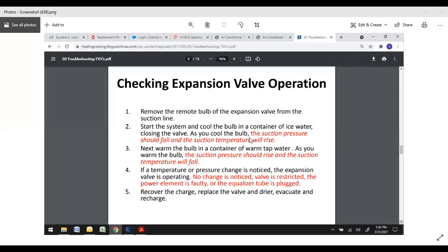Okay, well, you're checking the expansion valve. This is actually fairly easy because with Rheem, it's actually outside the cabinet. So the best way to check this is to remove the remote bulb of the expansion valve from the suction line. You can start the system. Two ways you can do it, or both, to verify you have a good test. First, you can cool the bulb in a container of ice water. As you cool that, the suction pressure should drop dramatically, and the suction temperature will rise. If you put it in a glass of ice water and you get little to no change, you've got a problem. You can also warm the bulb up.